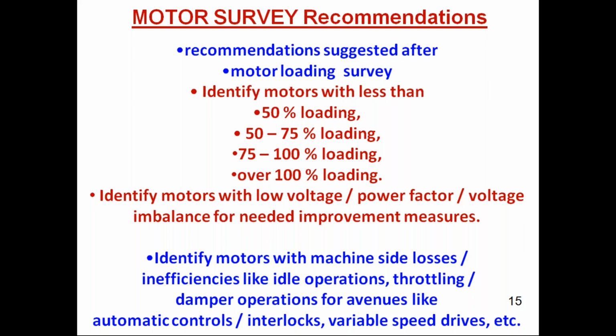In some of the industries where we have done energy audits, we suggested that instead of a 75 kilowatt, they change over to a 90 kilowatt compressor. The industry then said, sir, my motor breakdowns have also reduced and my energy savings have also been achieved. Any motor operated between 60 and 80% will definitely give the first point of energy savings. We are normalizing the energy consumption for the given motors. If the motor is operating at only 30%, let us say, we can fit some retrofits.